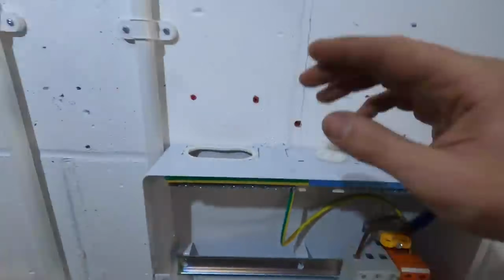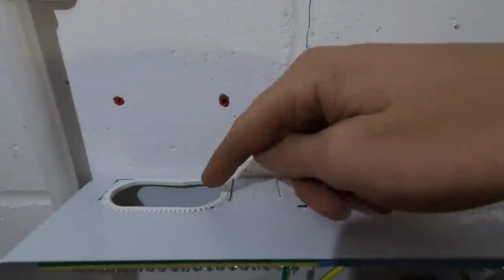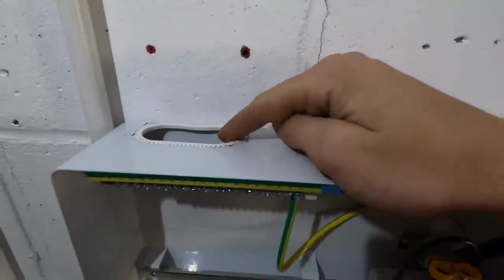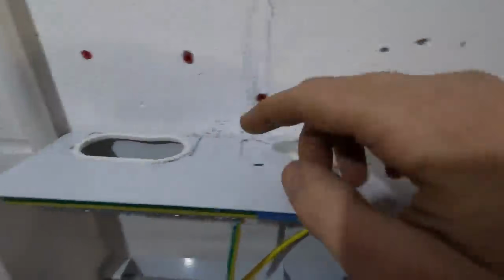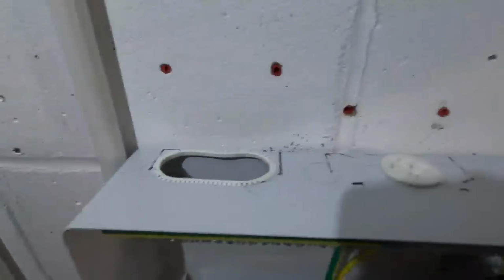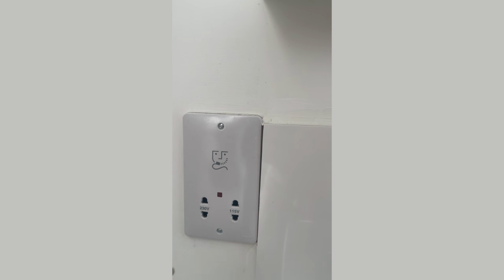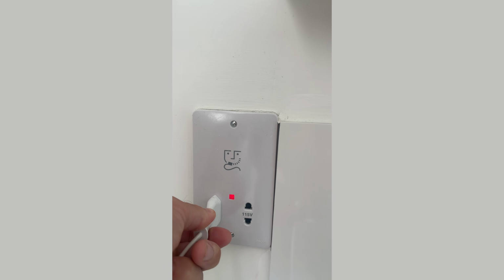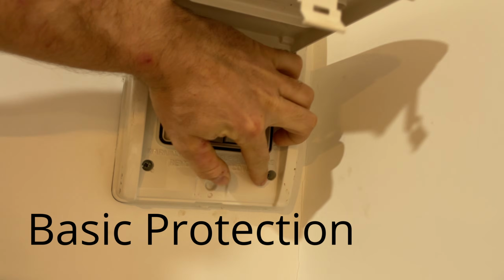You might think that electricians just install consumer units that are already up to regs, so it doesn't matter to them. Well, that's partially true. They do have to use consumer units that are up to regs, but they'll also potentially be drilling holes to allow cables to go into that consumer unit, so they need to make sure that when they're finished, they meet the standard. Another method of protection is an isolation transformer, which we find in bathrooms for shavers and toothbrushes. This means that there is no electrical path for current to flow through you unless you touch both the line and neutral to be completing a circuit, but that's very rare because of those barriers not allowing you to get to those wires.